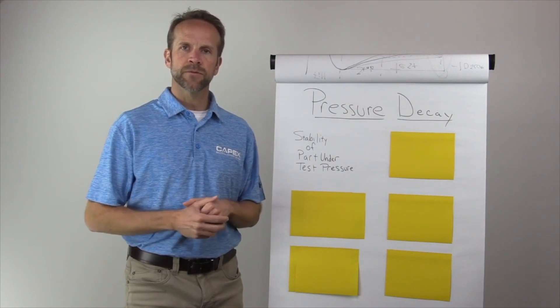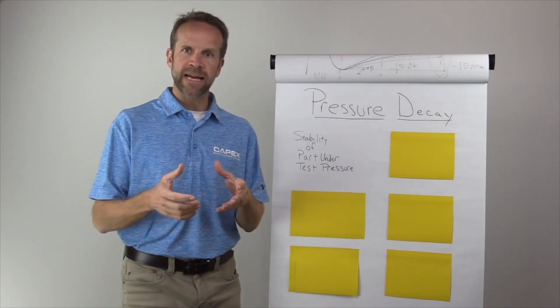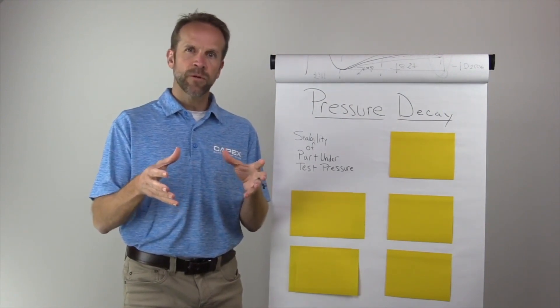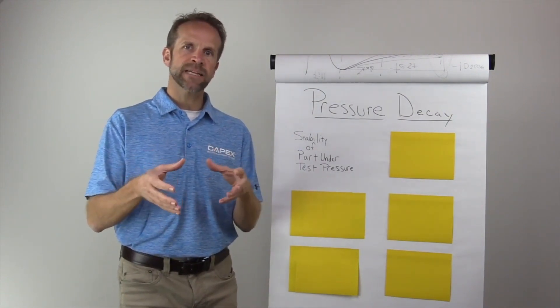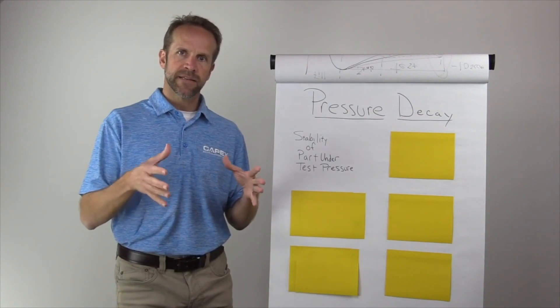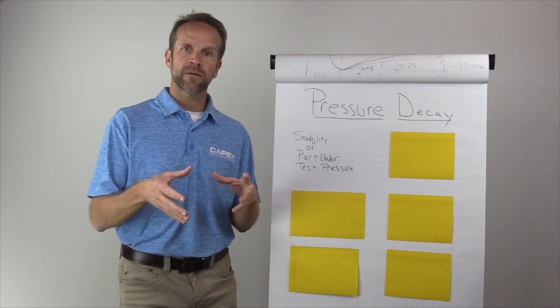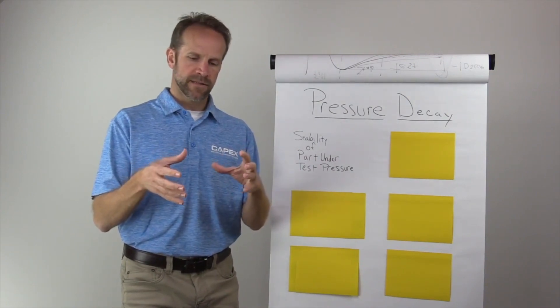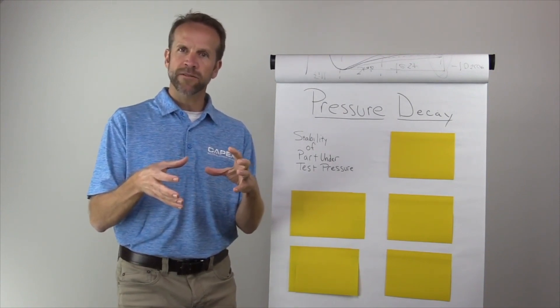The stability of your part under test is something to be considerate of. What that means is if your part is plastic and you pressurize a plastic part, let's say it's a windshield washer bottle, it's going to blow up like a balloon. And when we're using pressure decay, the environment inside the part is extremely critical because that's what we're measuring.